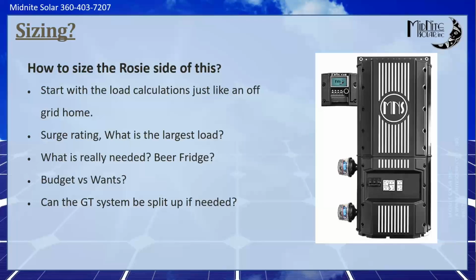Do they have a 5-horse well pump that's 1,000 feet in the ground, or do they have a half-horse well pump? Once you know their worst load they're trying to start, and if that falls into a single Rosie, a single Rosie will start their hardest load. Then you look at what they want to run combined together. Okay, they've got a fridge, a freezer, a couple TVs, some lighting. Maybe the max they've got is a couple thousand watts, which easily goes into a single Rosie.